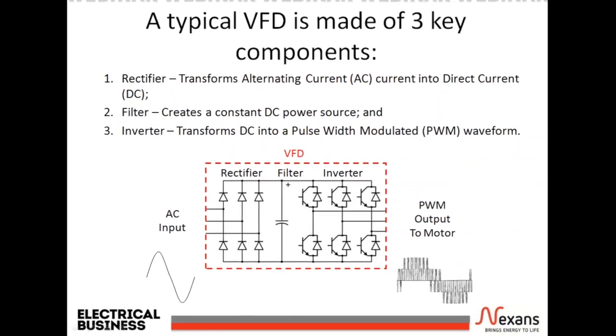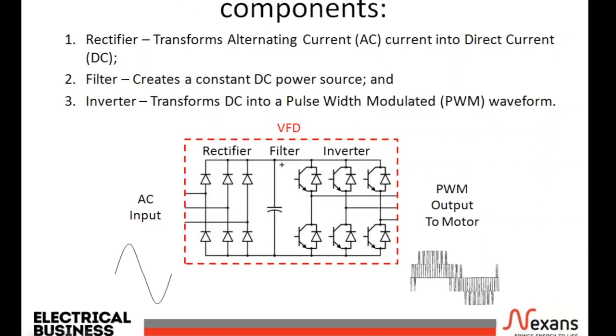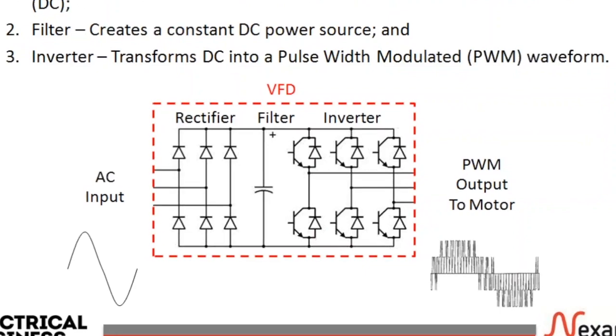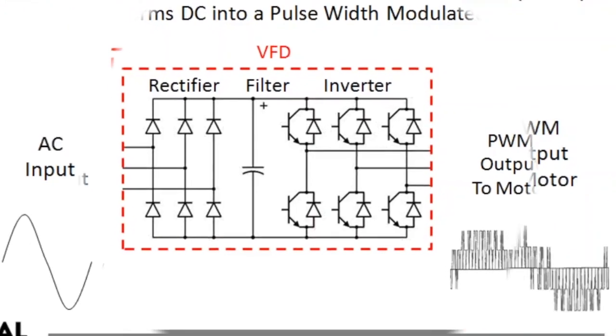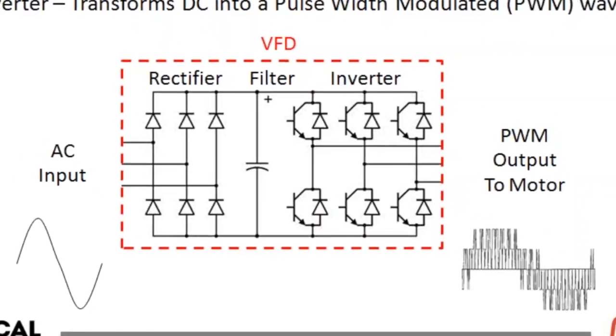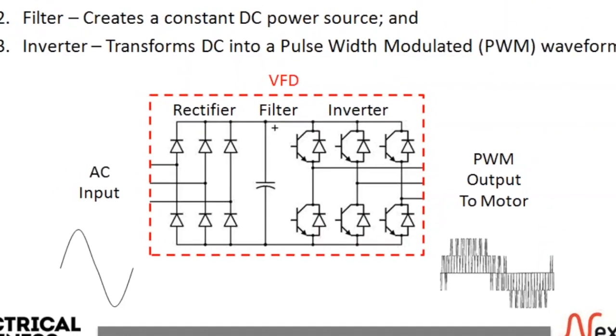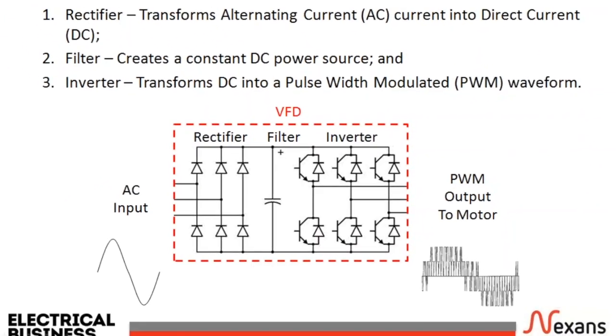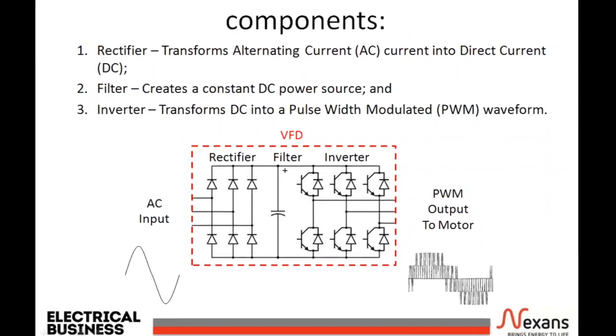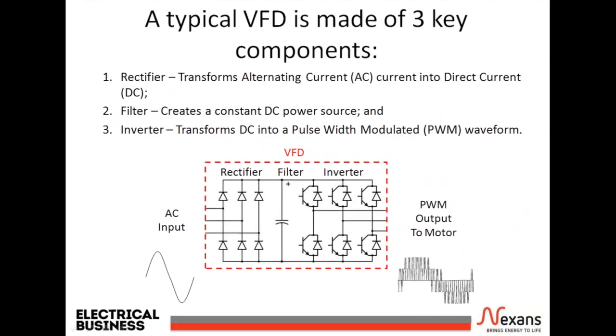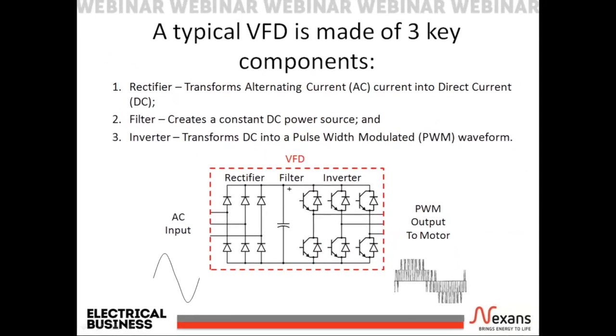Note that the input to the VFD is a sine wave, while the output is a pulse width modulated waveform, or PWM. The VFD is capable of varying the frequency and voltage of the fundamental waveform, or the lowest frequency component, thereby varying the direction, speed, and torque produced by the motor.